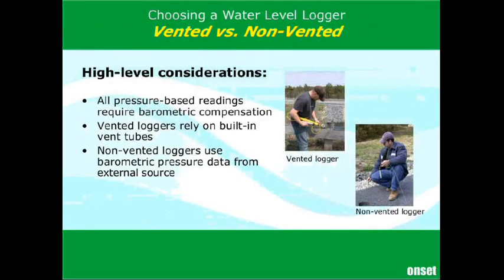A very critical area in your purchasing of the logger is a decision whether you want to go vented or non-vented. Let's just talk about what that means first of all. All pressure sensors measure the pressure or strain across a pressure diaphragm. In the vented logger, barometric pressure is brought to the backside of the pressure sensor diaphragm by way of a vent tube in a cable that needs to be extended above the water surface. The front side of the diaphragm sees the water pressure. The pressure measured by the sensor is entirely due to its depth in water.